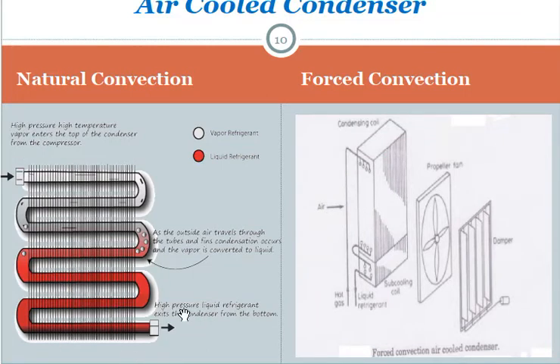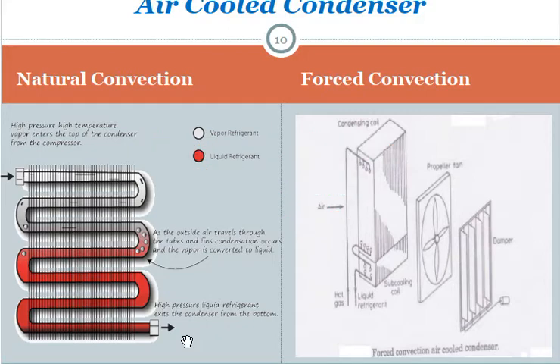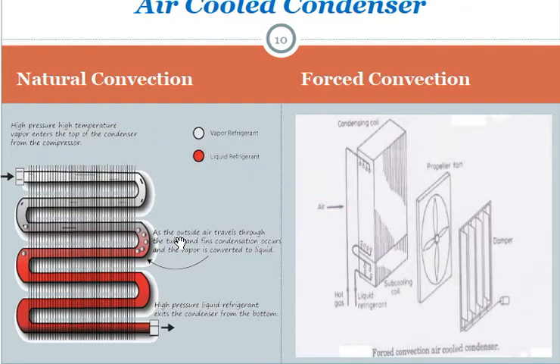Once the vapor changes to liquid, the high-pressure liquid refrigerant exits the condenser from the bottom at low temperature. For forced convection, a propeller fan is used to push air through the fins at high velocity, supplying more airflow than natural convection. This system is more effective but requires more energy for the fan motor.